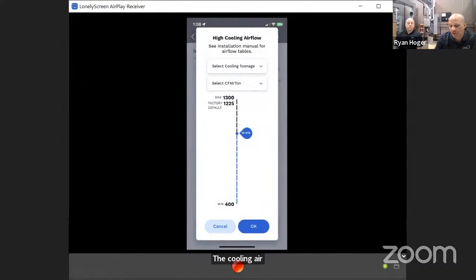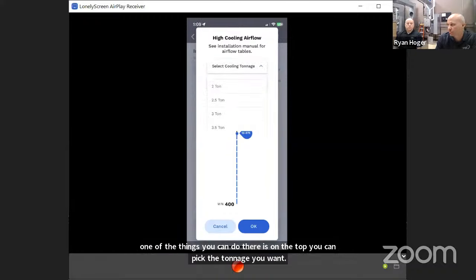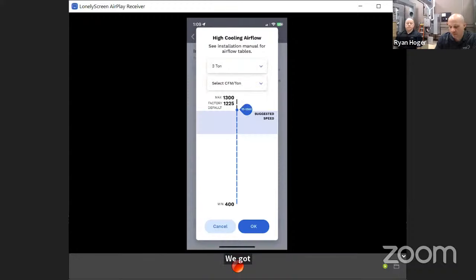So one of the things you can do there is on the top, you can pick the tonnage you want. I think we got this on, it's a 2-ton. No, it's a 3-ton, right? That one's on a 3-ton. So I pick 3-ton, and then I can select the CFM per ton that I want.